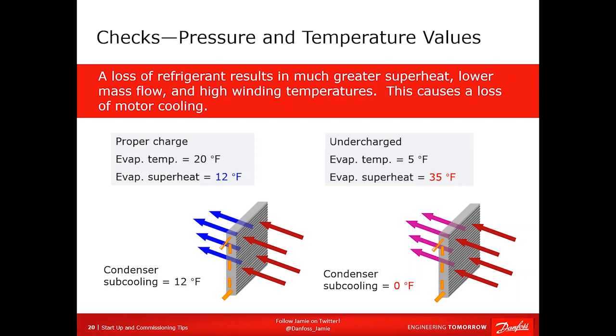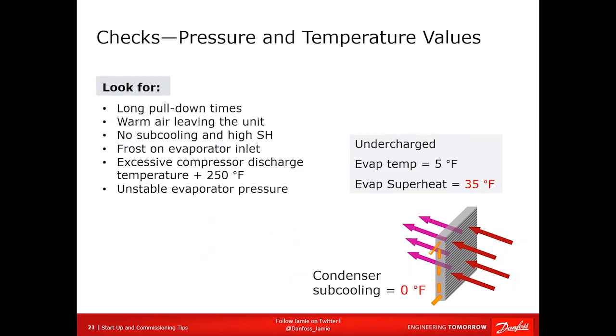Because if you've lost a compressor, say, for example, all right, then without you catching that leak, the same thing's going to happen. And if you don't catch the leak and you have this kind of condition, you're going to lose a compressor sooner or later anyways. So you might as well find that leak, correct it, and make sure the system is operating correctly. So what are you going to look for? You get to the job site, customer's going to tell you lots of stuff. Man, this thing runs, it never turns off. There's warm air leaving the unit and it's making that noise, but there's no cold air coming out, right? You're going to hear all this stuff.